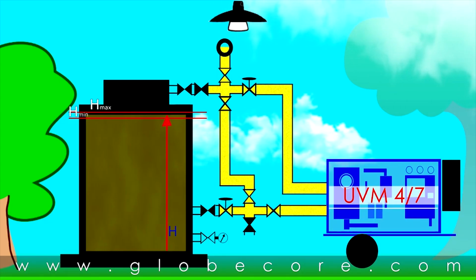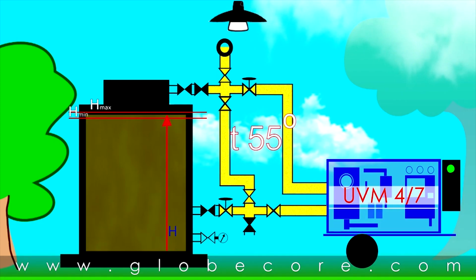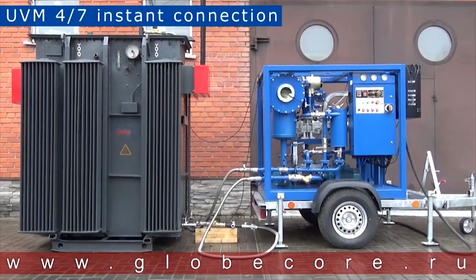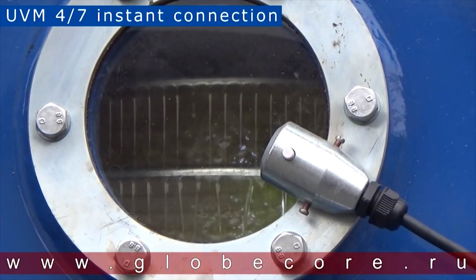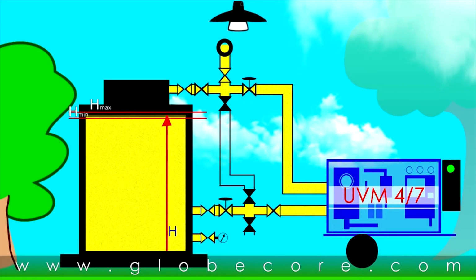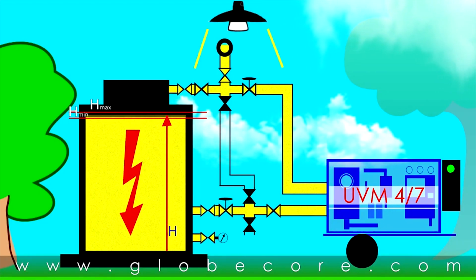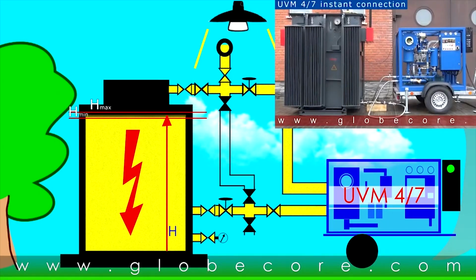When the temperature reaches 55 to 60 degrees centigrade, processing of oil in the transformer tank is commenced. After 15 to 30 minutes of stable operation, the transformer may be put online and processing will proceed for the required duration of time. This is the method of online transformer servicing.